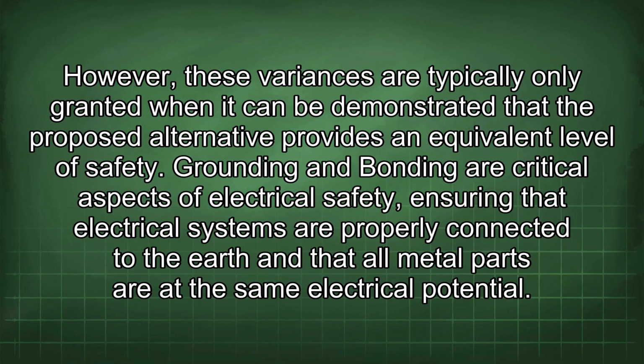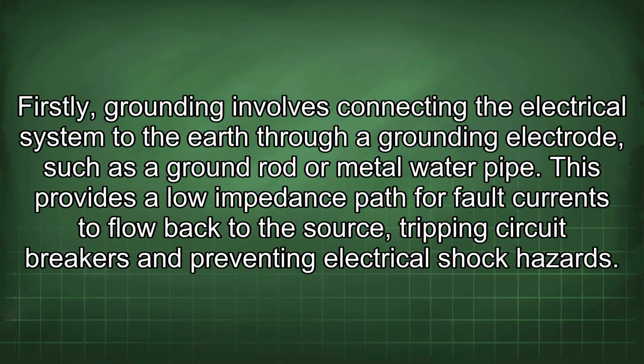of safety. Grounding and bonding are critical aspects of electrical safety, ensuring that electrical systems are properly connected to the earth and that all metal parts are at the same electrical potential. Firstly, grounding involves connecting the electrical system to the earth through a grounding electrode, such as a ground rod or a metal water pipe. This provides a low impedance path for fault currents to flow back to the source, tripping circuit breakers and preventing electrical shock hazards.